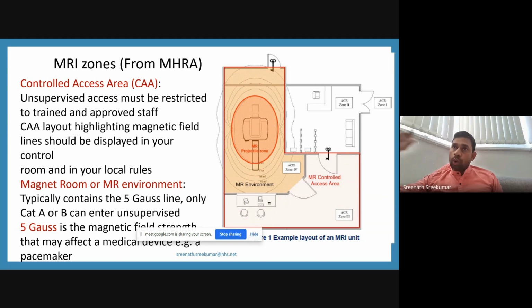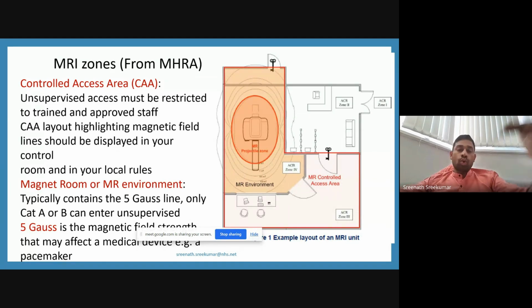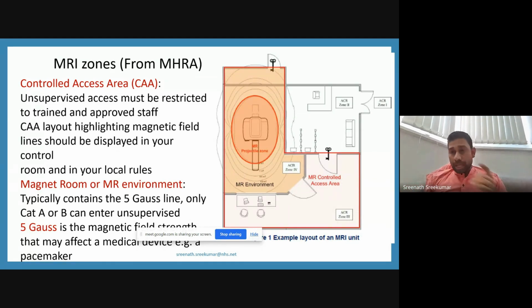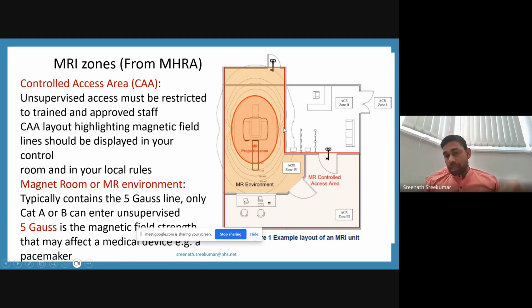We should follow that only a person with conditional devices should be allowed to go past the 5 gauss line. That's the one thing we need to mention. The projectile zone is inside the MR environment, but the 5 gauss line is actually the controlled access area, also included there.